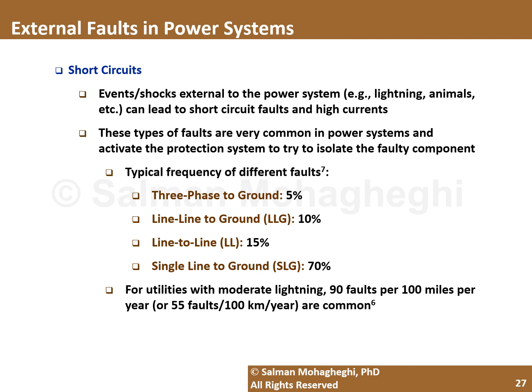So here we're going to be talking about just the external faults, the first category. One of the main categories of faults in power systems is short circuits, and these are basically due to different events, different causes, like lightning, animals climbing the poles, or birds flying in between the lines, or tree branches hitting the lines. And this typically leads to a short circuit situation and high currents. Different types of faults are three-phase to ground, line to line to ground, line to line, or single line to ground. With the latter being the most common one, and three-phase to ground, luckily for us, is the rarest one. Luckily, I say, because it would lead to the highest fault currents that could significantly impact the health and safety of other components.